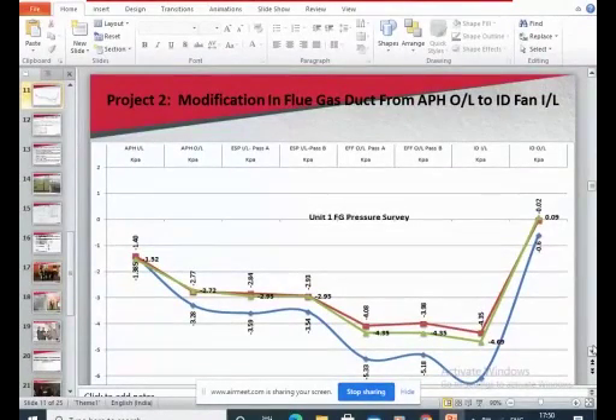This is the result. From the air preheater inlet to the ID fan outlet, the green line shows the design values, and the blue line shows the actual values when we took up this exercise. So it was far away from the design. Now after modification of this duct, the diverter plates were provided, and at the same points the pressure was measured again, and it shows an improvement, near to the design values.